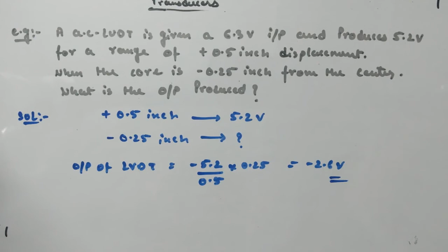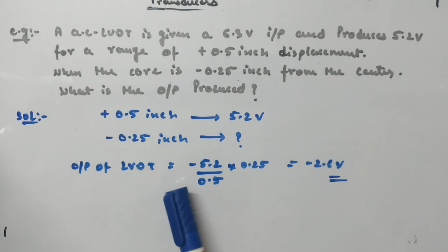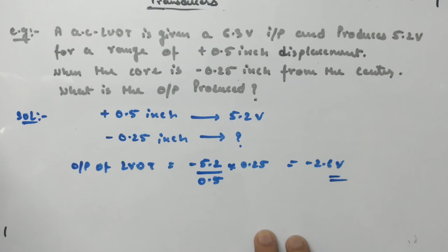So it is given that for 0.5 inch, the LVDT generates 5.2 volt at the secondary winding. So for minus 0.25 inch, what will be the output? By unitary method, output of LVDT will be 5.2 divided by 0.5, into minus 0.25, that will be minus 2.6 volt - that will be the output generated at the secondary winding of LVDT.